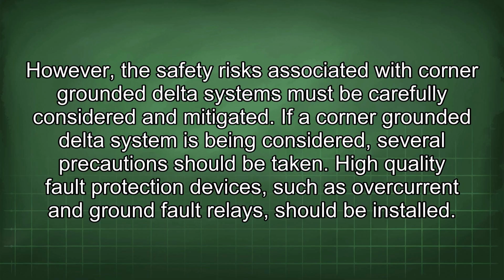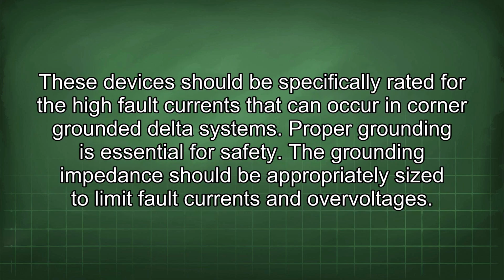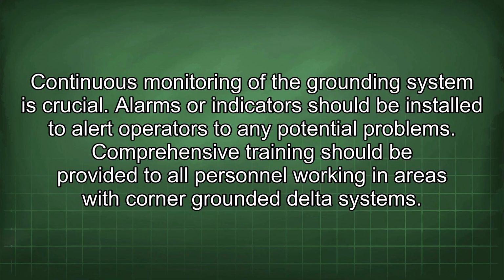If a corner-grounded delta system is being considered, several precautions should be taken. High-quality fault protection devices such as overcurrent and ground fault relays should be installed. These devices should be specifically rated for the high fault currents that can occur in corner-grounded delta systems. Proper grounding is essential for safety. The grounding impedance should be appropriately sized to limit fault currents and overvoltages. Continuous monitoring of the grounding system is crucial. Alarms or indicators should be installed to alert operators to any potential problems.